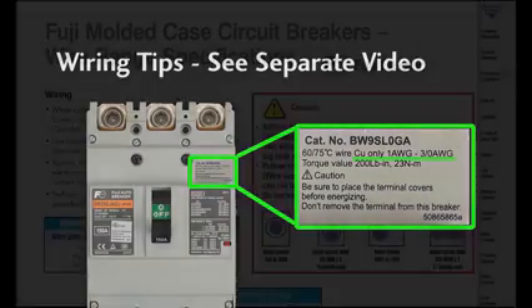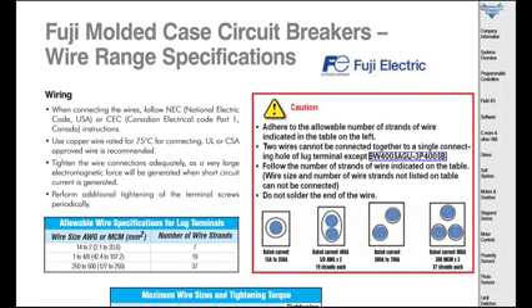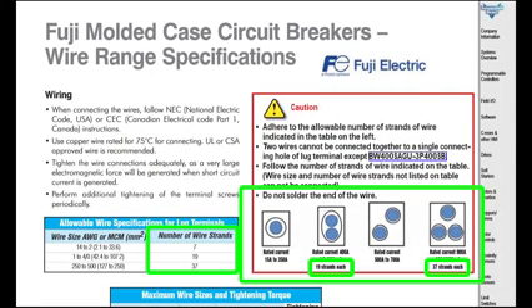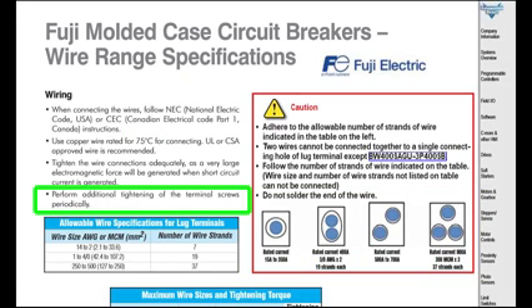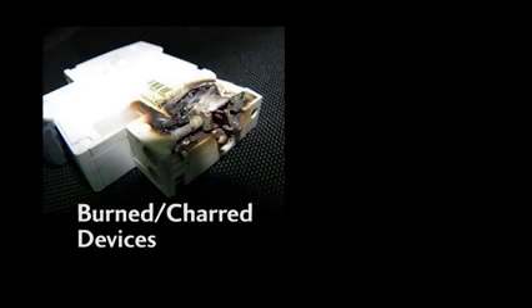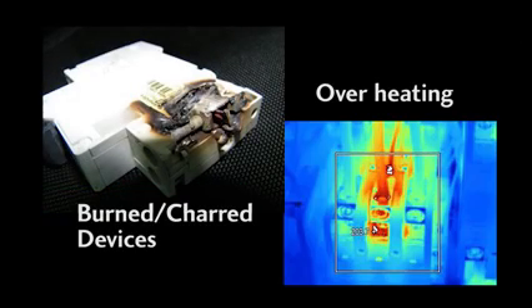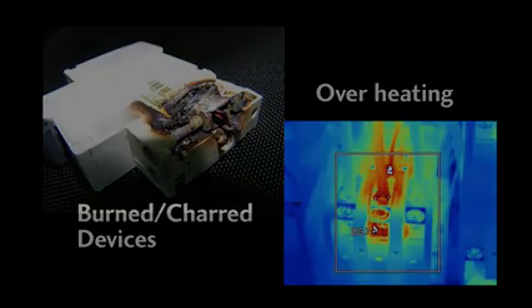Be careful to follow the wiring notes in the specs. There's a separate tech tip video on wiring, but just know that it's really important to follow the wiring guidelines in the spec sheets and that are printed on the terminals themselves. For example, this one shows you how many wires and how many strands in each wire are allowed for each terminal type and temperature range. Also note that they recommend retightening these terminal screws periodically, so consider adding that to part of your regular maintenance schedule. If you don't pay attention to wiring specs, bad things happen, so please pay attention to those and check out that tech tip video on wiring.